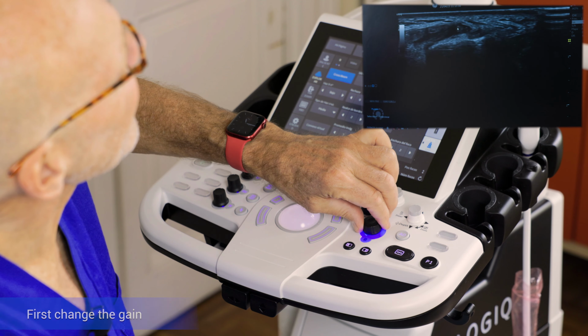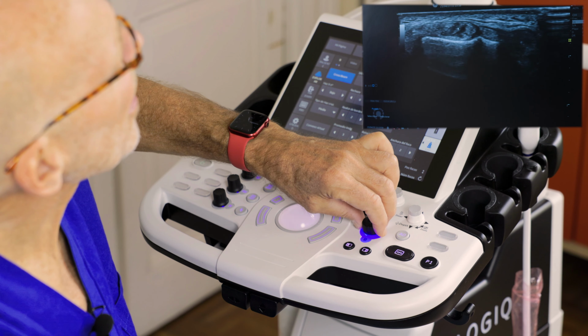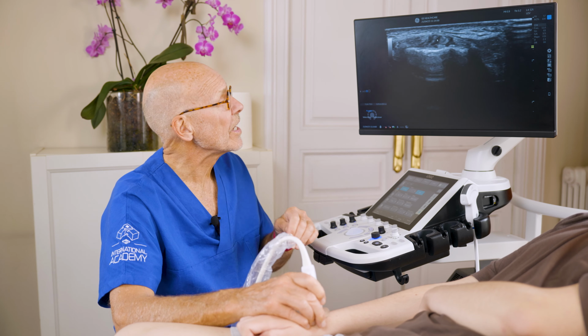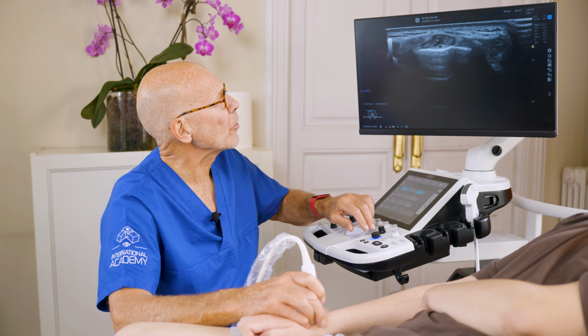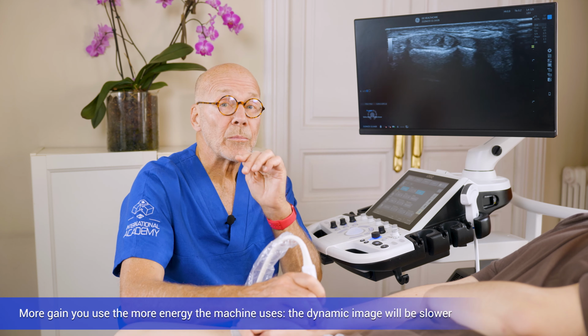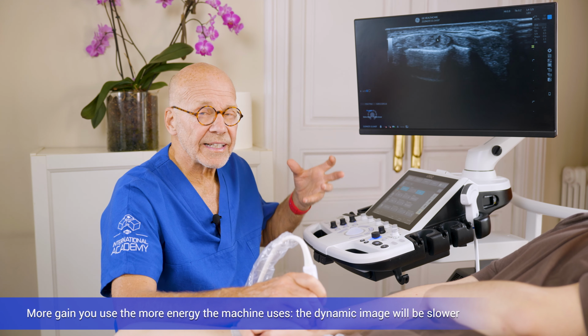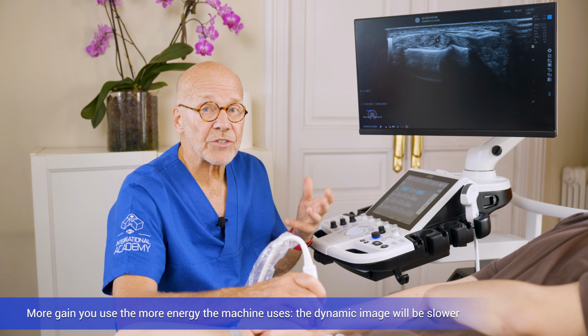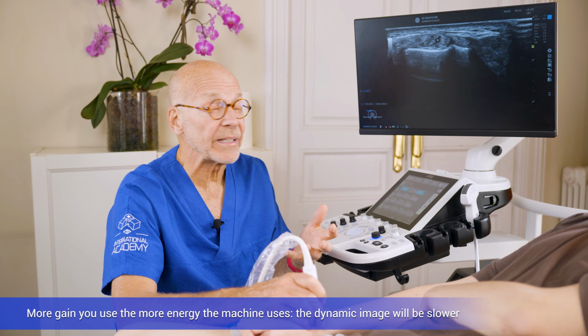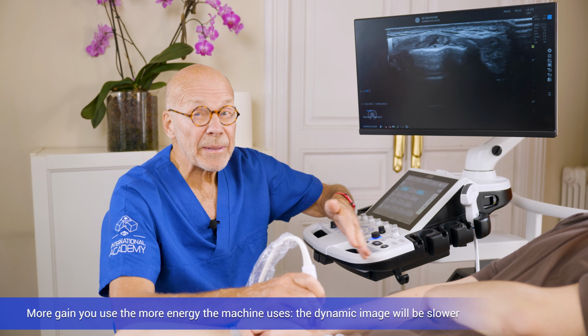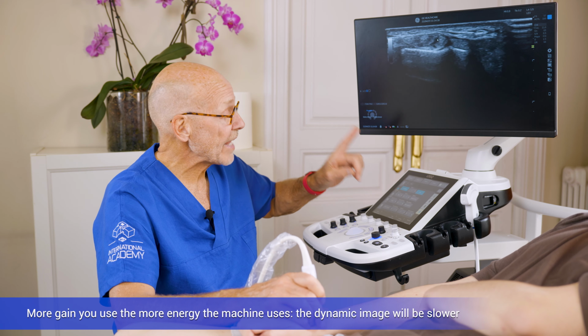I like a little more contrast, so this is kind of where I like it, but it's really your preference, the amount of gain that you're going to use. Remember though, the more gain you use, the more energy the machine has to utilize. So it may slow down your frame rate a little bit, so your image may lag behind the movement of your probe. So that's gain.